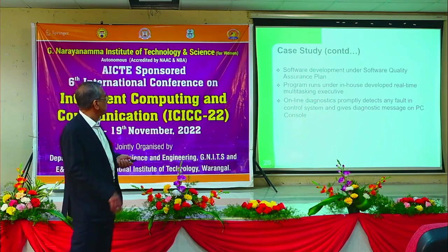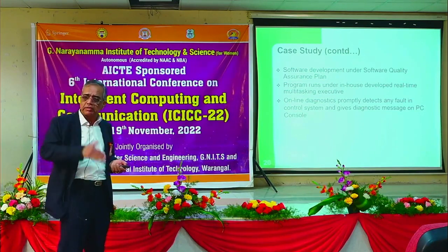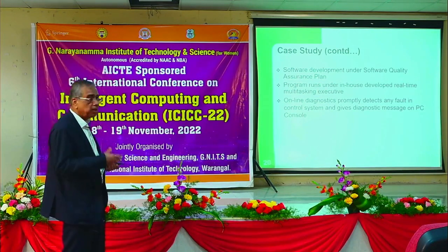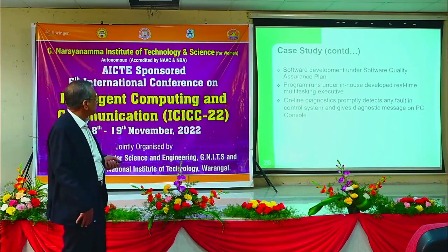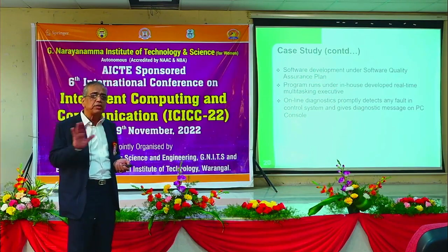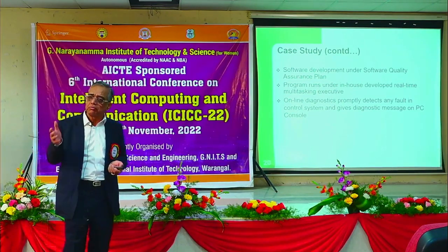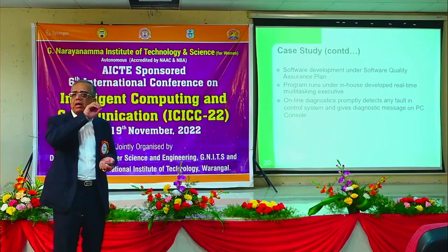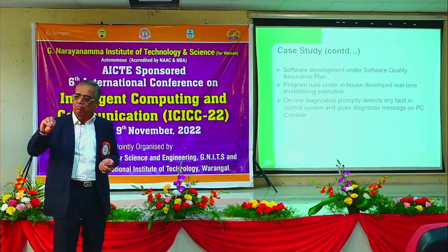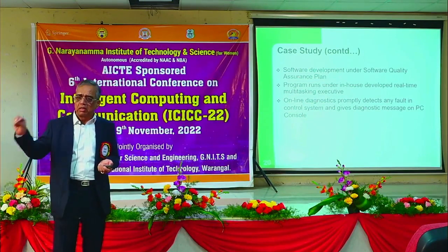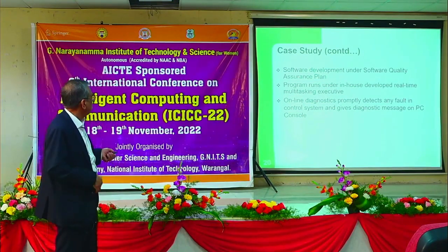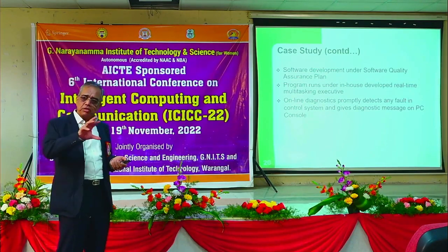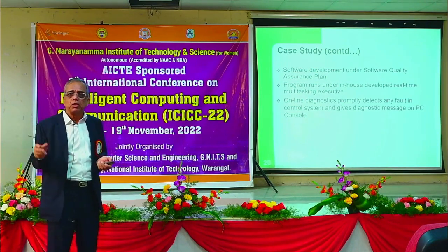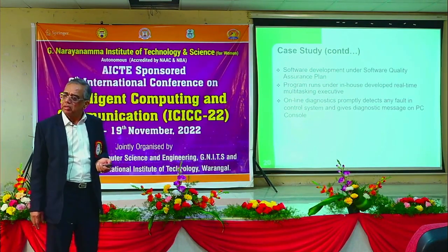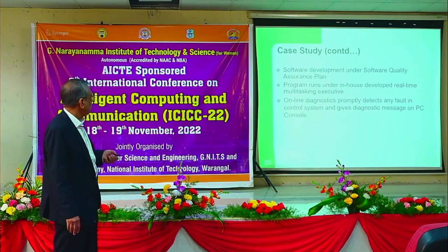Software development is under a software quality assurance plan. I told you the various stages under document preparation and verification by an independent team. The program runs under an in-house developed real-time operating system. We do not use any operating system from outside, no commercial one. It has to be a small executive to do data acquisition, processing, output, and online diagnostics in the 100 millisecond time; it is designed like that. Online diagnostics promptly detect any fault in the control system and give a diagnostic message immediately, so that any faulty board can be replaced immediately online.